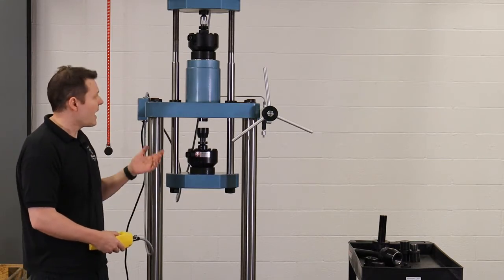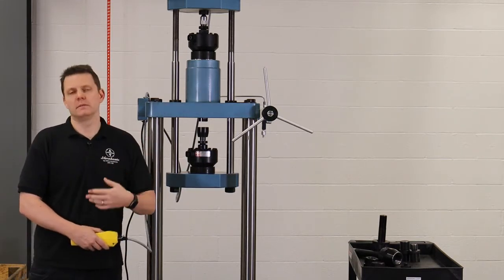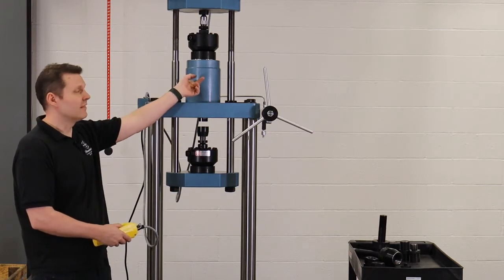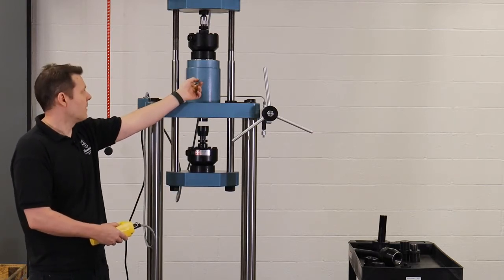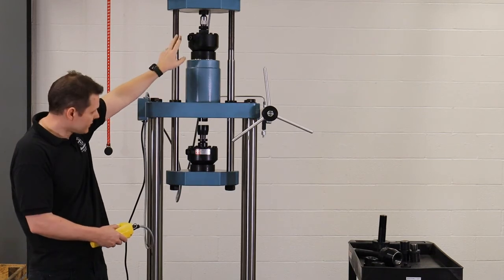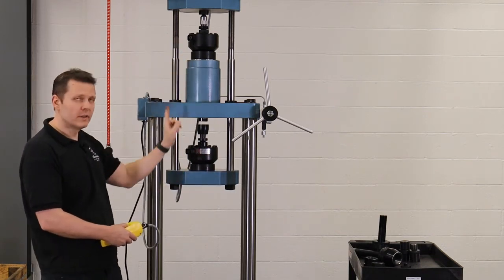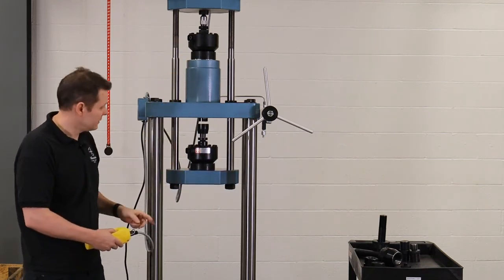When we start pumping the jack, we're going to put fluid into this. The hydraulic fluid is going to raise the ram up and this is always going to be moving in this direction. This machine, the UCM, is a machine that the reference standard always stays in compression.